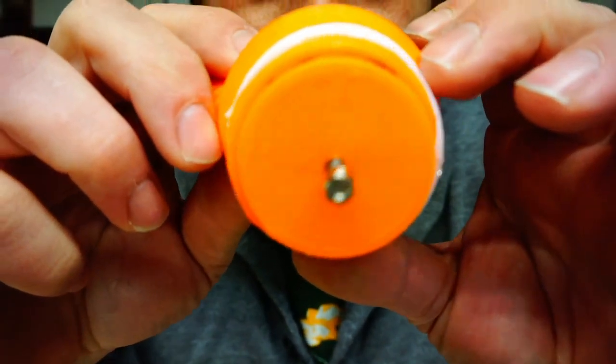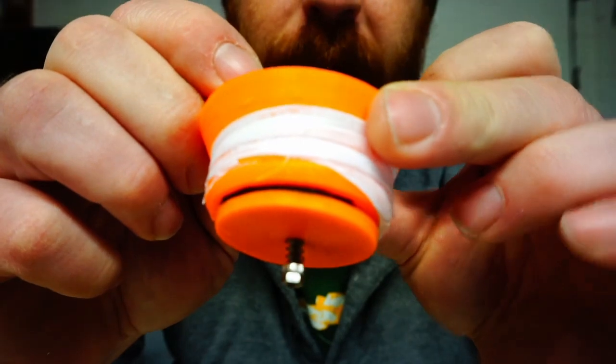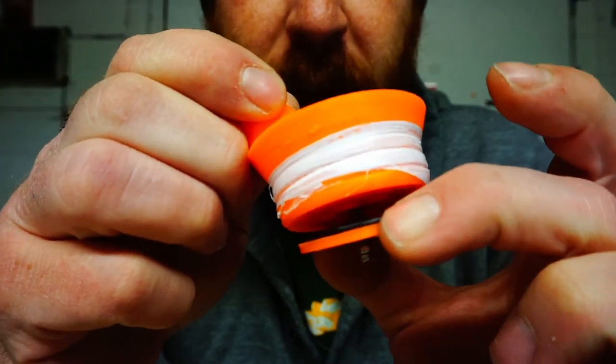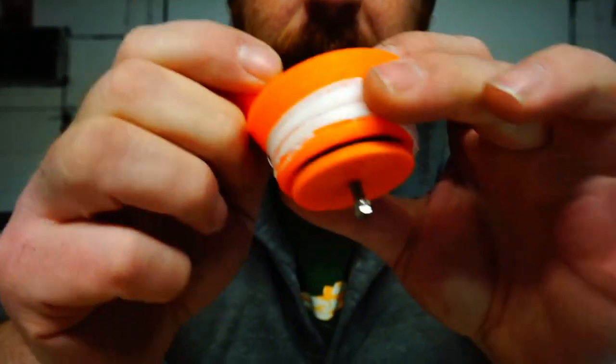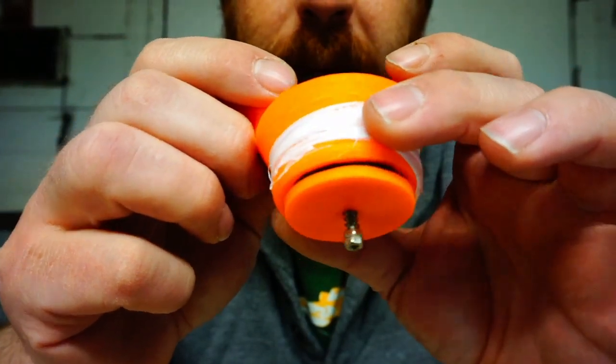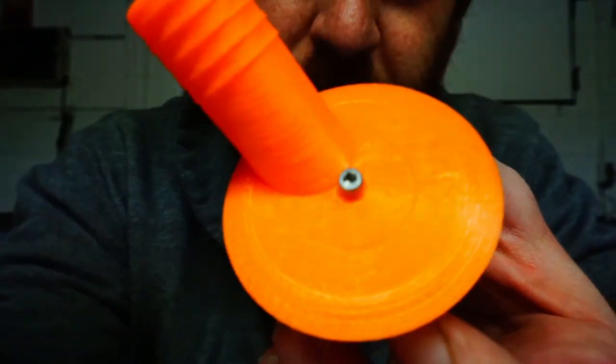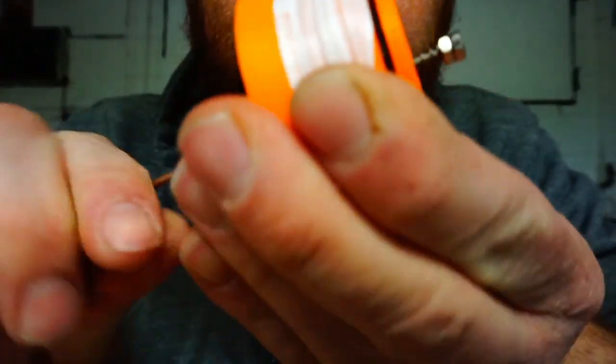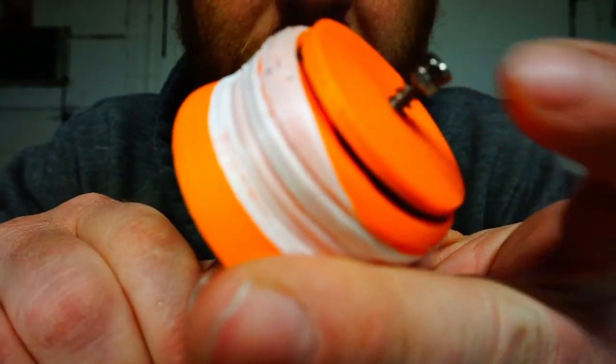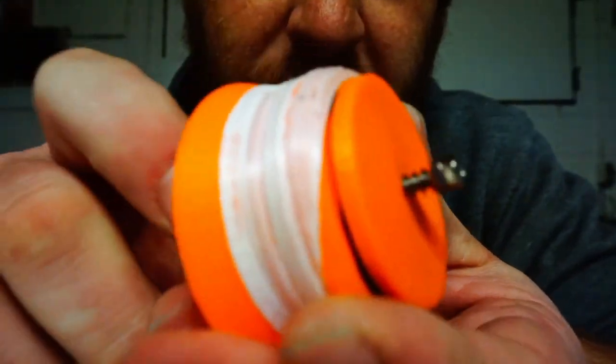And so the best solution for this guy would be definitely to use a solenoid valve and a pressure sensor and use an Arduino or some sort of microcontroller to control the PEEP pressure, which is the pressure positively forced back to the patient during exhale. But this is manually adjustable. So when you turn this screw in the top, if you back the screw off, what you're doing is bringing these two lock nuts up and compressing the spring, thereby adding force to the diaphragm, and when you add force to the diaphragm, you need a higher pressure to push the diaphragm away from the orifice plate and giving a higher exhale pressure.